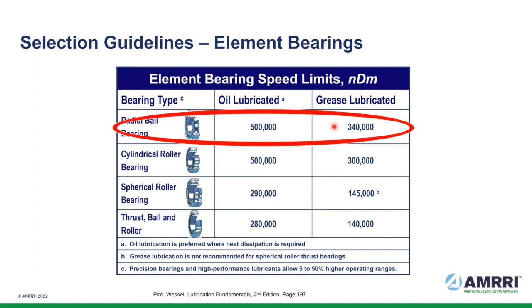operating temperature range, viscosity limits for high temperature and cold temperature conditions, operating conditions. Shaft speed cannot be overstated. The shaft speed is a huge influence in your final decision. And then lastly, regardless of what the machine builder says, go back to the component builder. Look at this through the prism of the bearing manufacturer and beg the question, if we can make the right product choices, do we really need AW/EP chemical characteristics? Most of the time we don't.